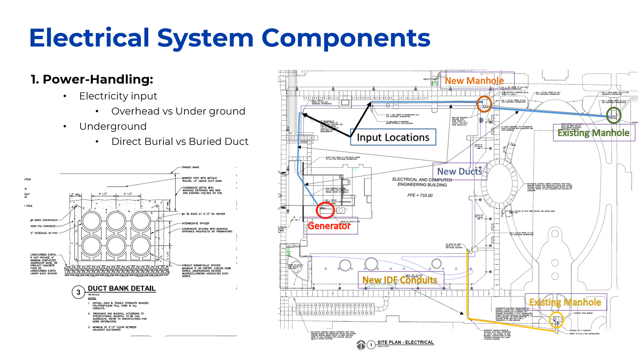The most important component is the unit substation, an assembly comprising a primary voltage switch and fuse or circuit breaker, a step-down transformer, metering equipment, controls buswork, and secondary low-voltage switchgear. Its main function is to accept incoming high-voltage power, transform it to a lower voltage usable in the facility, and distribute it through associated low-voltage switchgear.